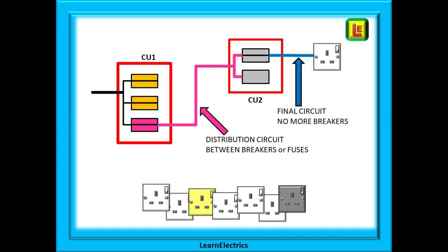Now let us take a cable from the consumer unit into the garage and terminate it into a second consumer unit for use in the garage. The cable that connects the two consumer units is not a final circuit — there is another set of breakers to go through in the second consumer unit. This is called a distribution circuit; it is distributing electricity from one consumer unit to another. The cables leaving the second consumer unit going into sockets or lights are final circuits, as they have no more circuit breakers to pass through.